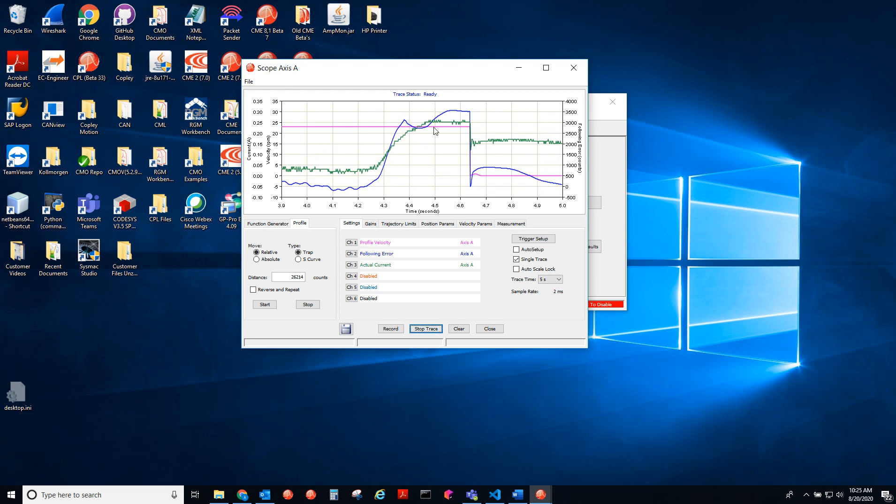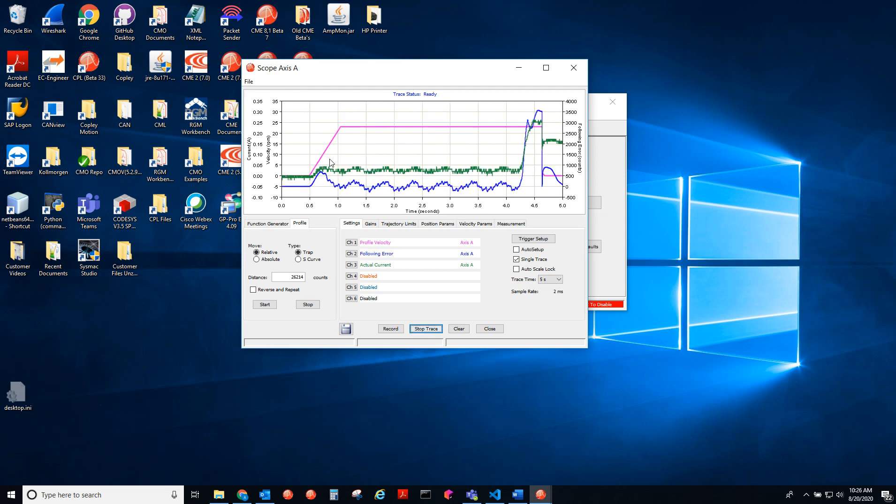So once the current exceeded 0.2 amps, that's when the homing routine is referenced and the profile velocity went to zero.